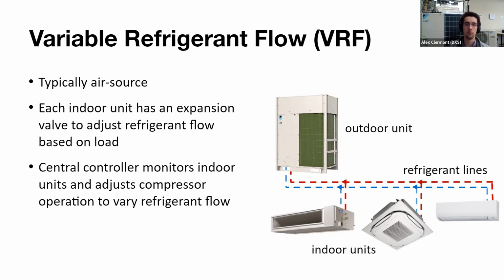The outdoor unit will in turn modulate the compressor to adjust the amount of refrigerant it's sending to all the indoor units. The outdoor unit can also be twinned up to three different modules, so they can become quite large, and that's all depending on the design requirement of the very specific building. We'll get into efficiencies for these types of systems a little bit, but these systems are really good at part load. At full load, they're pretty good, but they really shine at part load.